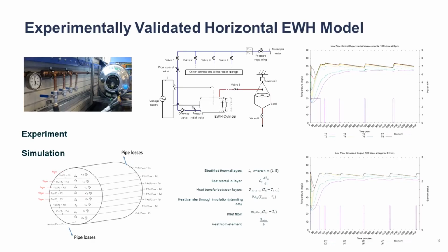The simulation, I really looked at a multi-nodal analysis, which had a bunch of layers within the tank that had heat transfer between the layers and heat transfer between the layers and the environment. I set up particular layers for the element, and we've got mass coming in, so that's the inlet coming in, and the outlet, which I don't have logged over here, but it was an important point.